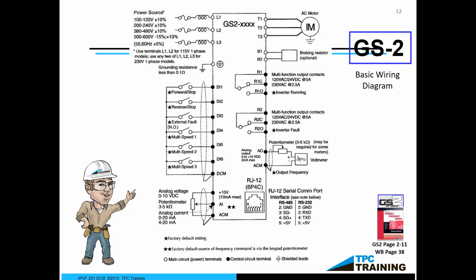There on the right-hand side, you can see that we have what they call multifunction output contacts. Maybe you want to satisfy a fire alarm system. You need to know that this system is running and up to speed. You can program these multifunction output contacts, when the drive is at speed, to open or close. So those two are programmable. Each one of these digital inputs or relay outputs are all programmable. There's a buffet of options. Maybe you want to know if there's a fault. Maybe you want to know if you're under speed. Maybe you want to know if you're over speed. Whatever the case might be, you'll be able to program these things for your application.